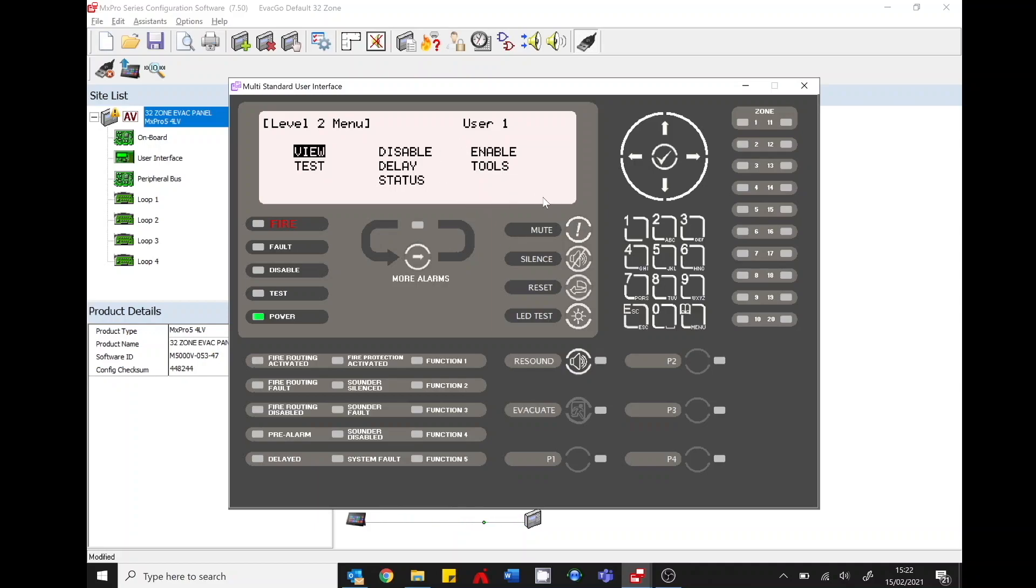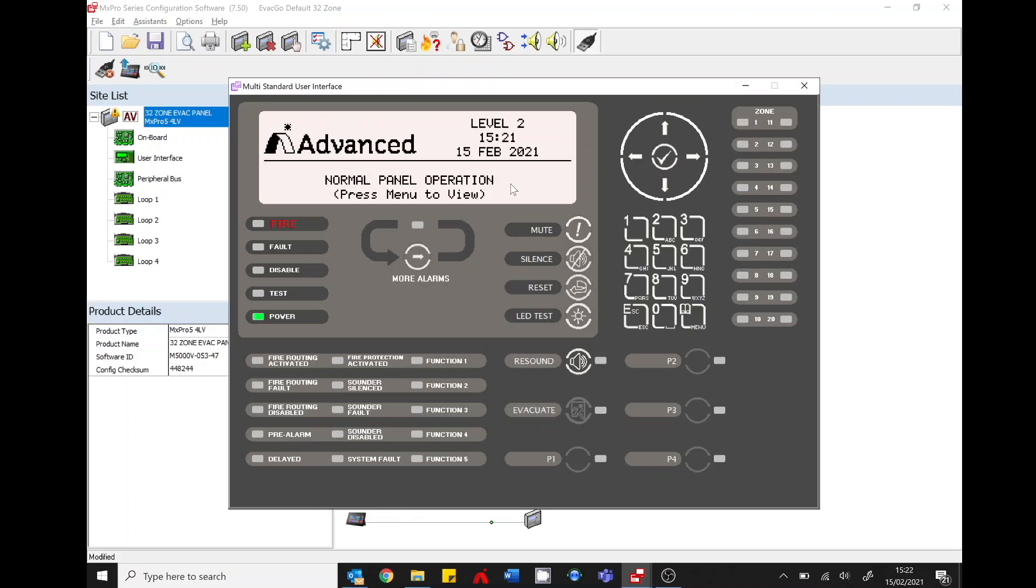Just remember the evacuation system has a general fault LED. We have configured this general fault LED to illuminate when the panel is in programming mode. So when it's basically a reminder just to give you indication that the panel is in level three. So do remember to put back to level two before leaving site. Thank you for watching and stay tuned for further videos.